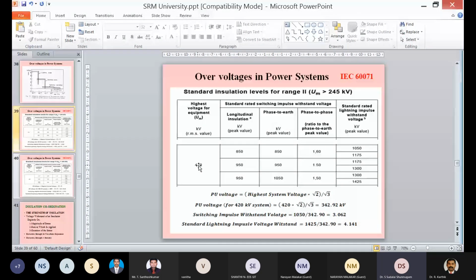Again, for a 420 kV system, the per unit value is 342.92 kV. Again, the same formula I used: highest system voltage times root 2 divided by root 3. That will be the per unit value for a 420 kV system, that is 342.92. And the switching impulse withstand voltage is nothing but 1050 divided by 342.92. You see here, now it is peak. Earlier it was RMS. In power frequency, it is in terms of RMS. When it comes to switching impulse, it is only peak. Therefore, the switching impulse withstand voltage is equal to 1050 divided by the per unit value, which is nothing but 3.062.